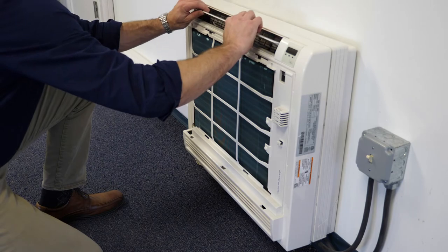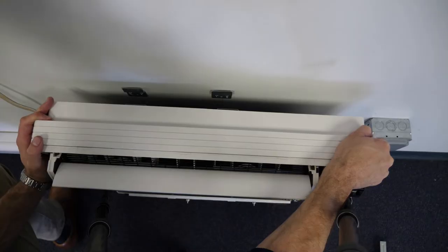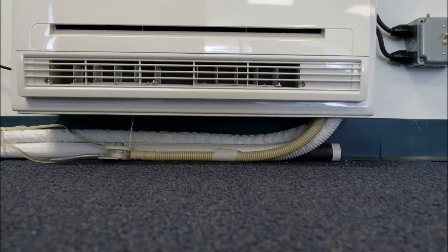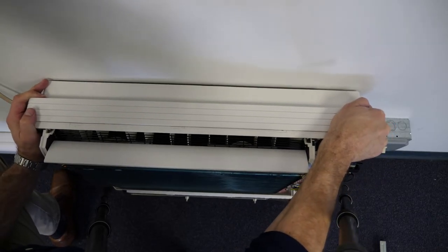The panel may then be removed by lifting up and forward over the louver blade. When installed vertically, the unit ships with a mounting bracket intended to be anchored to the wall. The bracket should be installed to provide for a recommended four inches beneath the unit to help facilitate drain and refrigerant connections and serviceability. The unit is then slid vertically down onto the bracket.